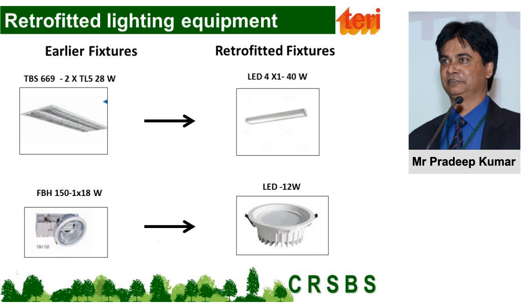So what we in fact did was measure the lighting levels at different work planes. Also, we collected all the information: the type of fixtures, the type of lamps, and everything used. What we noticed was that the lighting levels provided at different work planes were not up to the recommended, or rather visual comfort, level. The client also told us that he will not take up anything which saves less than 40% energy. So it was very challenging for us, as we first had to improve the lighting level to the required visual comfort and show that savings of up to 40% can be achieved. This was the challenge at the starting point.